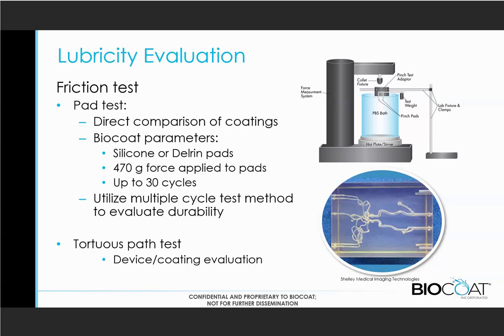The other way of doing this is to look at the entire device with its coating in a simulated use model, like a tortuous path model, where you can measure the trackability as it's going through some sort of simulated anatomy, which gives you a nice evaluation. You can do that either by tactile feel, or even by attaching a load cell to it and then measuring the force as it's going along through there.